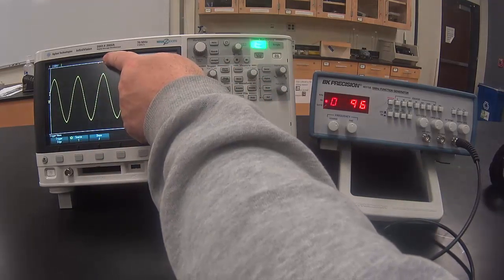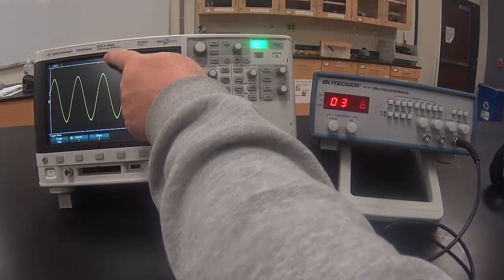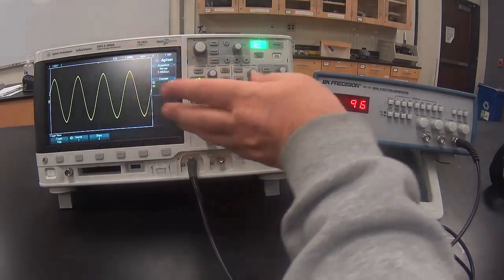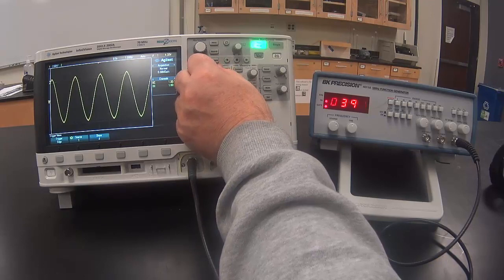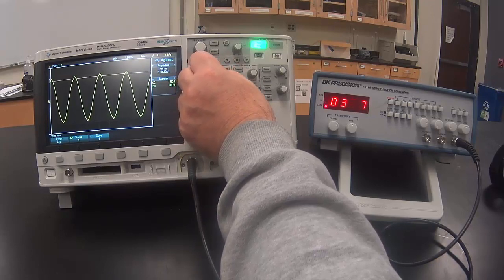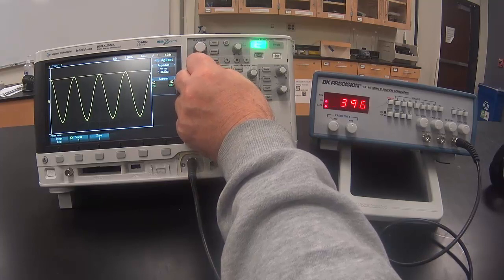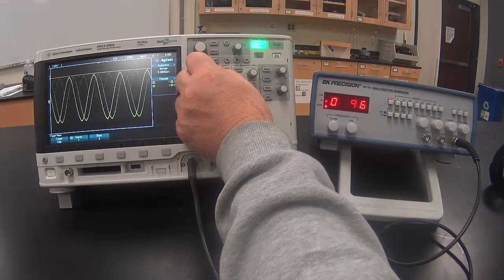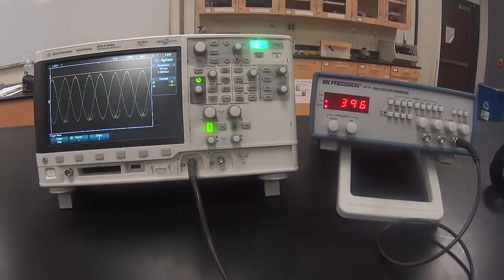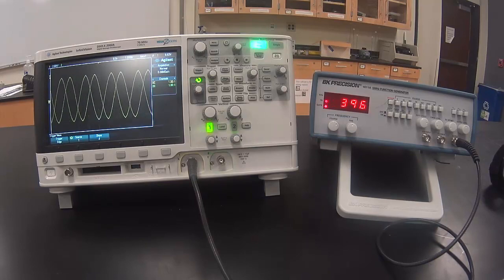At the top of the screen is an orange triangle. The trigger level is a voltage. The voltage level that the trigger is set to is the voltage that you will see the signal at under the orange triangle on this particular scope. If the trigger level is raised above the voltage of the signal then it doesn't know when to start drawing the signal and you get an unstable signal or on some scopes no signal at all.